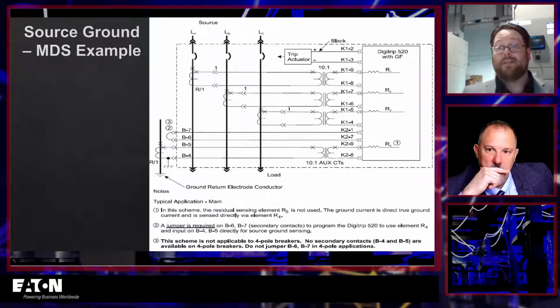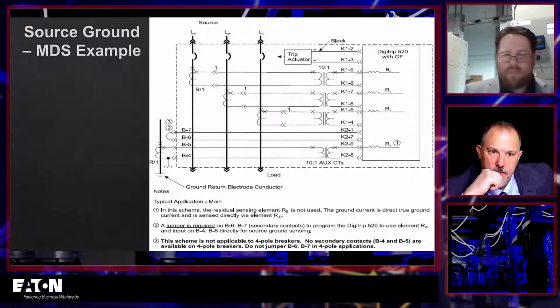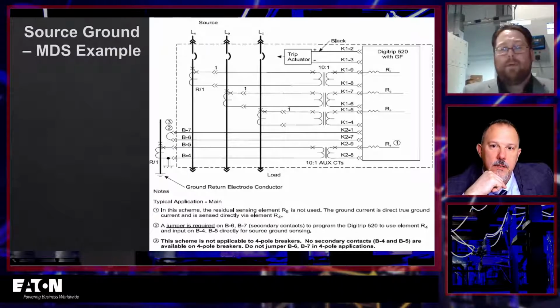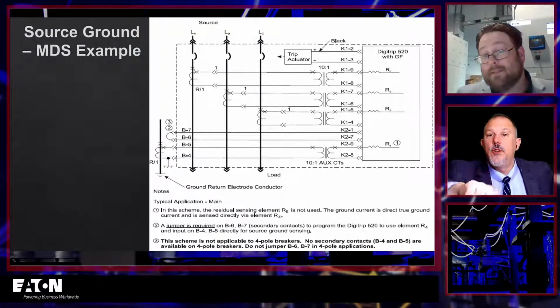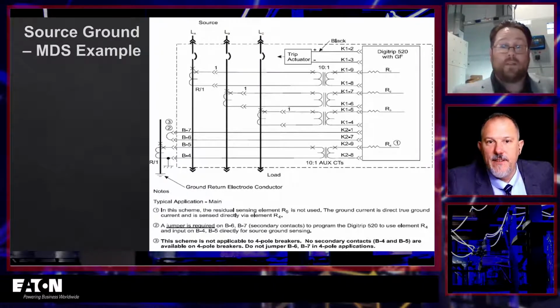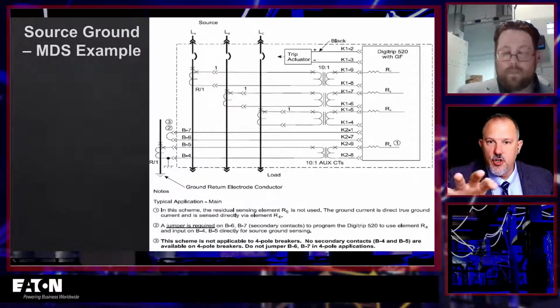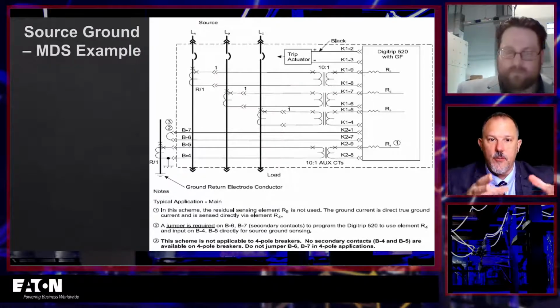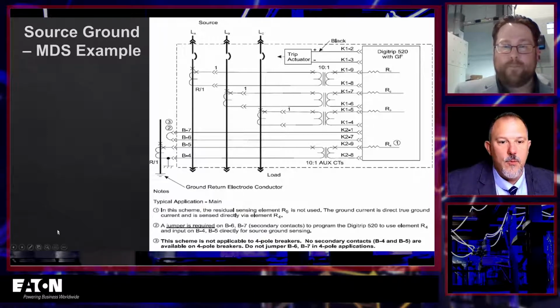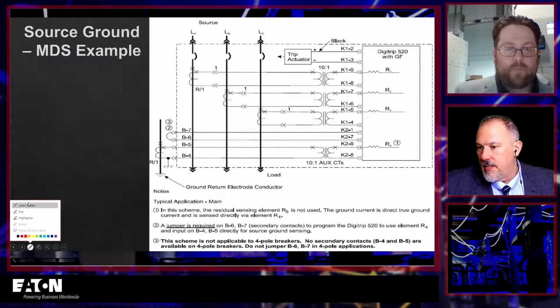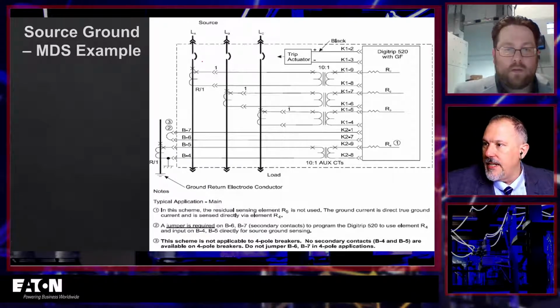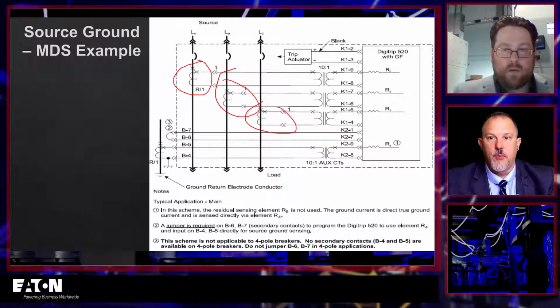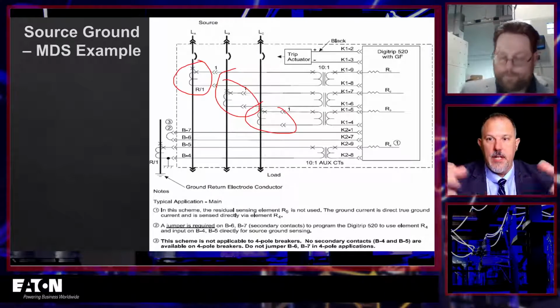And that's why we want to do the test, because we're human. We make mistakes. We miss jumpers, put jumpers where they don't belong. We want to confirm that. Now in this case, it's a Digitrip 520, and we're showing the trip unit, but that trip unit is in a circuit breaker. So the CTs that we are showing right here are all a part of the circuit breaker. That's all built into the circuit breaker.